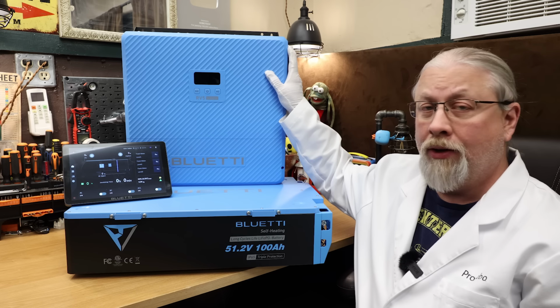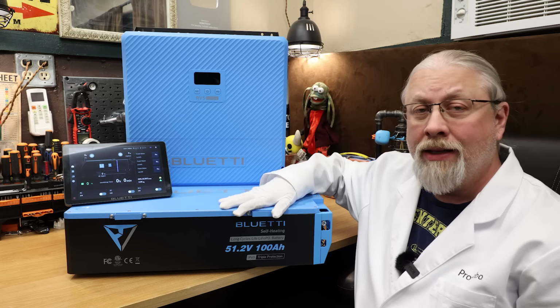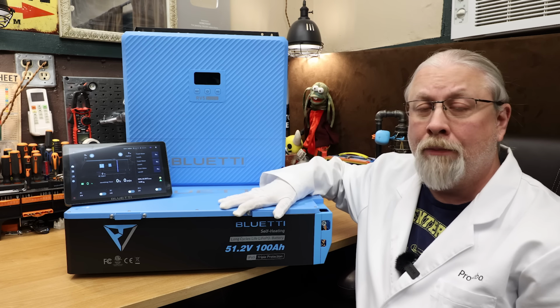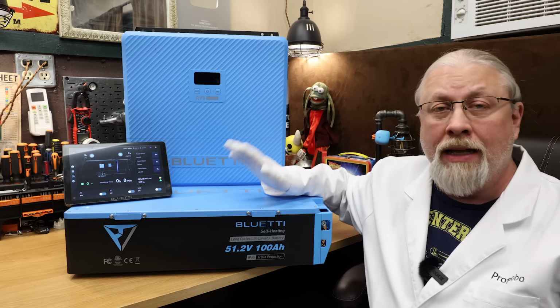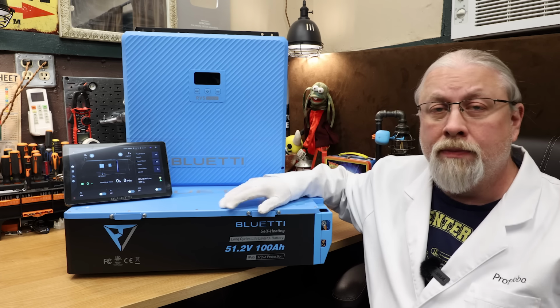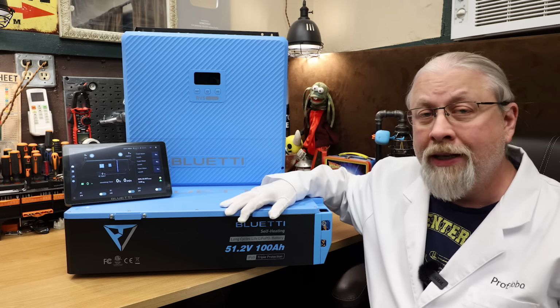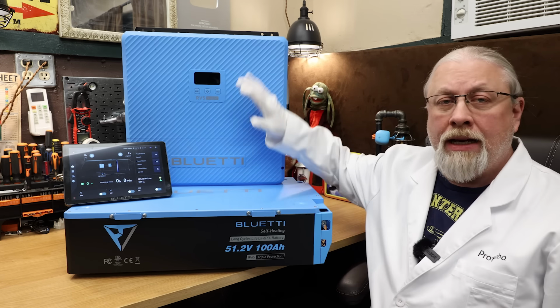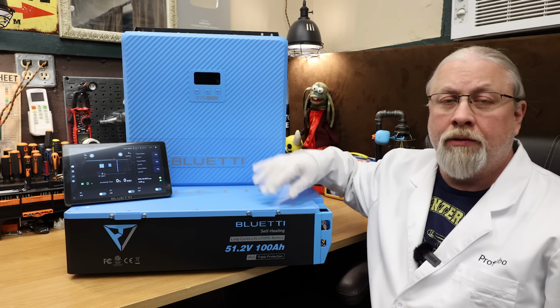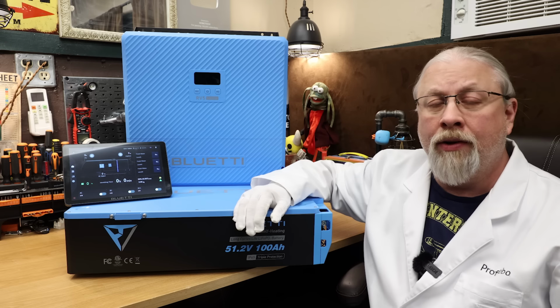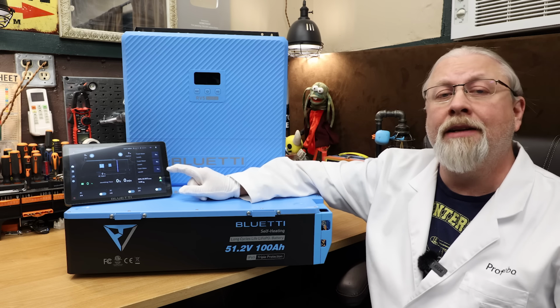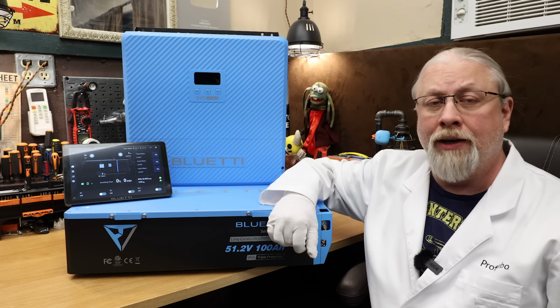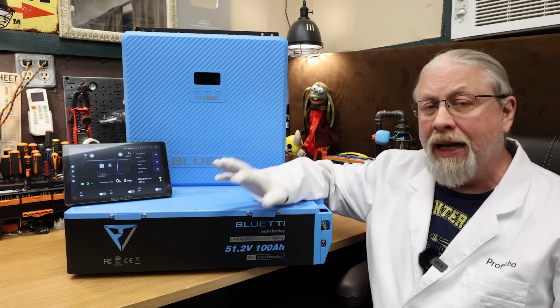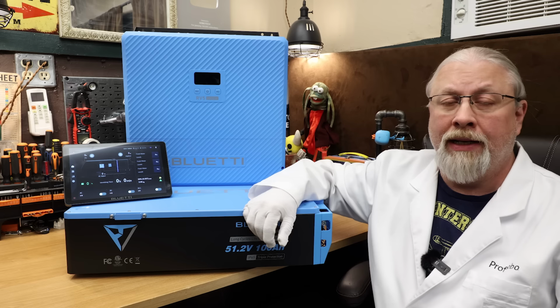As this is not outdoor rated, while installing the sealed and heated batteries in a separate wet or cold environment. And since the batteries are modular, you can install as many as you have room for, up to 24 batteries. The batteries and inverter communicate with each other through a single Ethernet data cable, and you can install an optional screen in a different location for remote monitoring. Essentially, it lets you build a bigger system in a smaller, more limited environment.